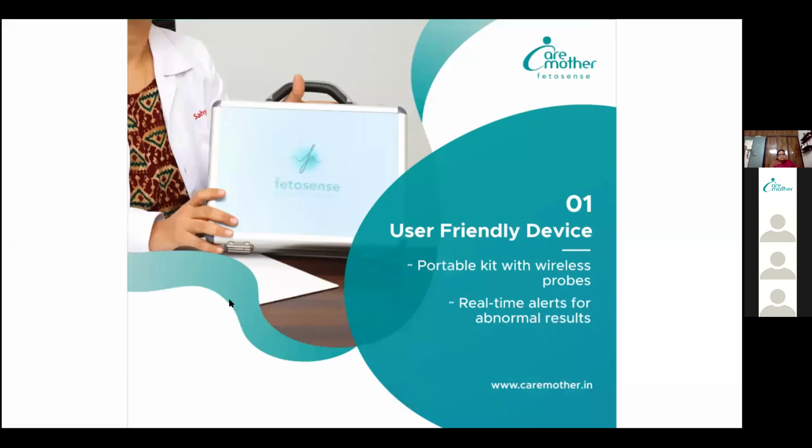A couple of features make it different from the conventional CTG machine. As you see, it is completely portable. The dimensions of the kit will be something around 1 foot by 10 inches and it weighs around 1 kg. So it is absolutely weightless in nature. You can move it around in the OPD, IPD, labor room without any effort. It doesn't require a cart.